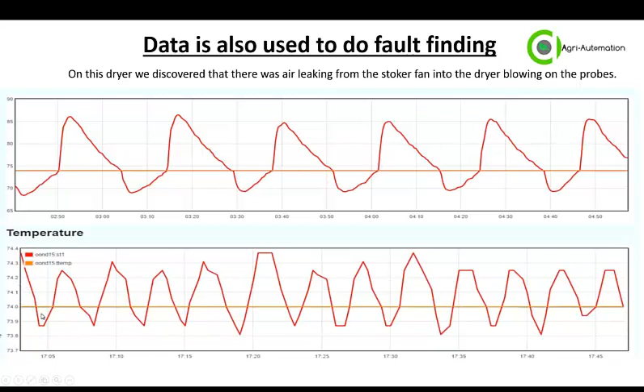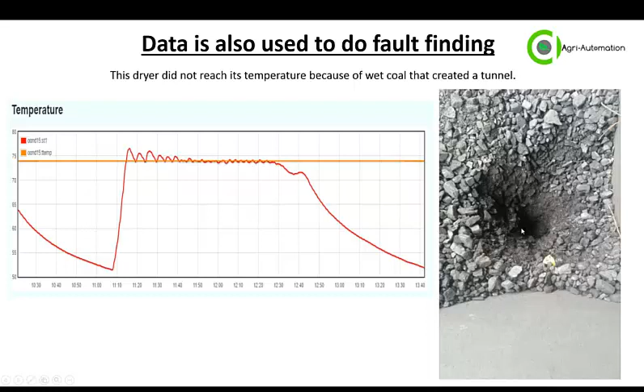We would also see temperature not being reached because of the coal creating a tunnel of coal that's dirty or wet. So this is basically what would happen. You would see the arches come down as it got less and less coal, and then at one stage it could not get onto temperature, and then the safety kicks in. It switches off the stoker, and then it lets you know that there's something wrong, and that's why you'll see this huge dip.